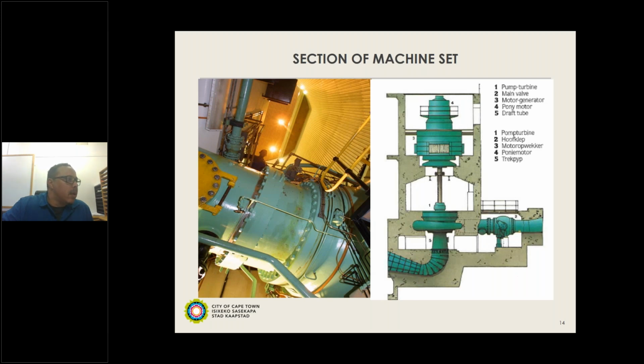The third portion would be in the middle here, which is the heart of your electrical component. So inside section 3 here would be your gen stator, and also your rotor rim, rotor hub, and your 10 rotor poles, which I've shown you on the previous slide, but we will show some more photos a bit later. On top of the unit, each of our machines has what we refer to as a pony motor, and the pony motor serves a dual purpose. So when we operate under gravity, we are generating, and we do not use the pony motor to start up in generate mode. We utilize gravity.